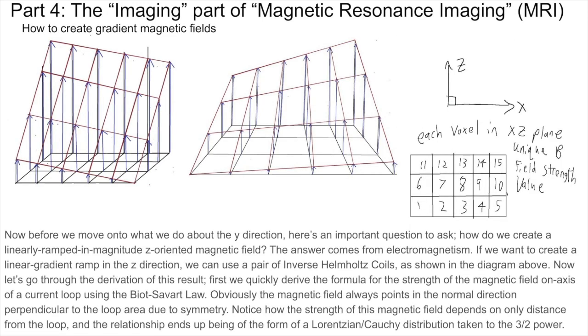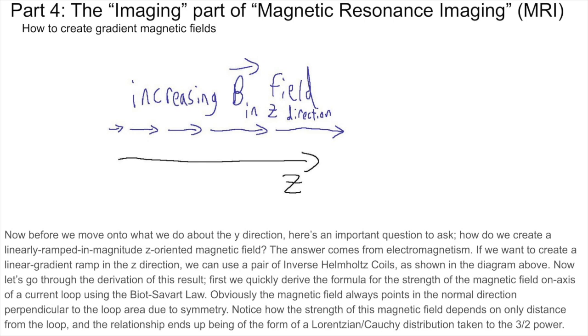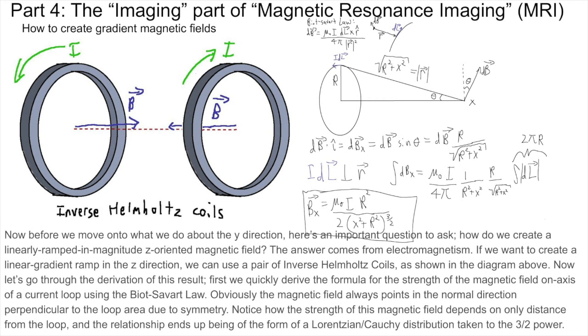Throughout all three-dimensional space, each voxel has some magnetic field vector with some magnitude pointing in the Z direction. Now before we move on to acquiring image data in the Y direction, here's an important question: how do we create a linearly ramped and magnitude Z-oriented magnetic field? The answer comes from electromagnetism. If we want to create a linear gradient ramp in the Z direction, we can use a pair of inverse Helmholtz coils as shown in the diagram above. Now let's go through the derivation of this result. First, we quickly derive the formula for the strength of the magnetic field on axis of a current loop using the Biot-Savart law.